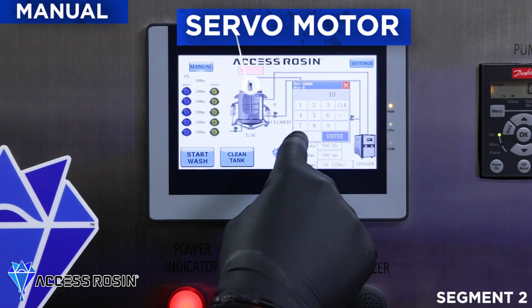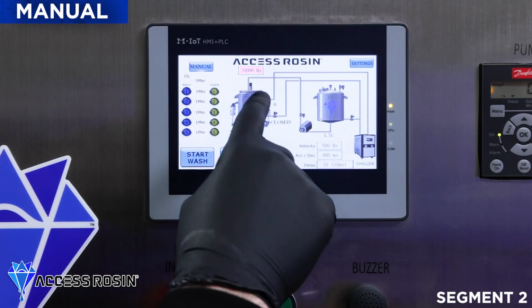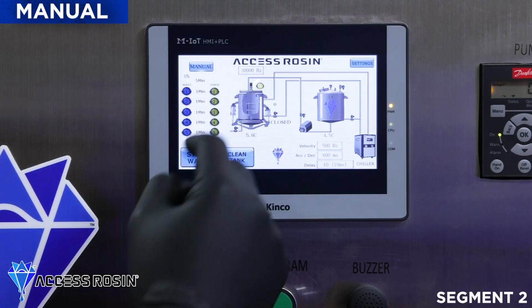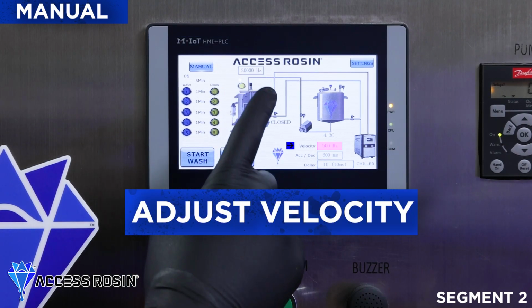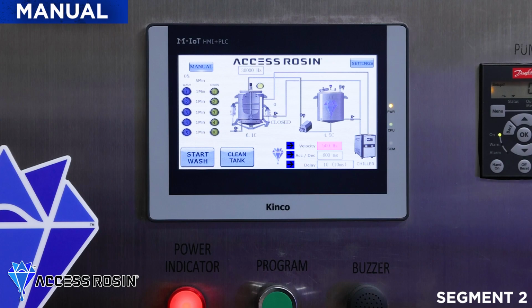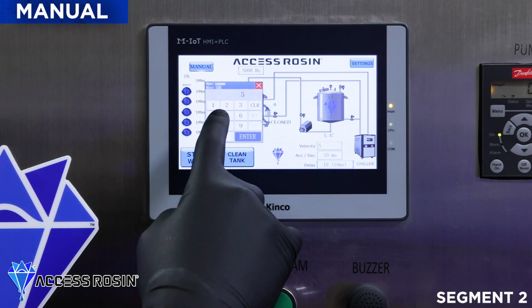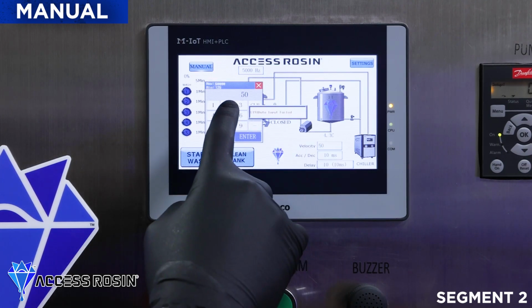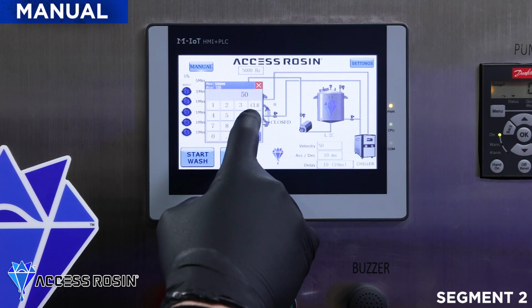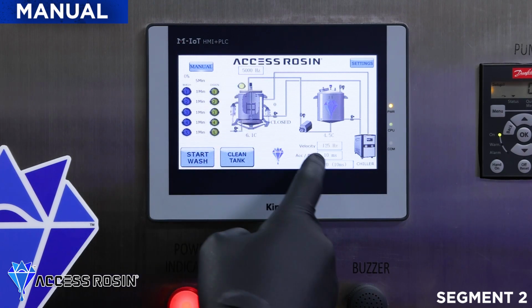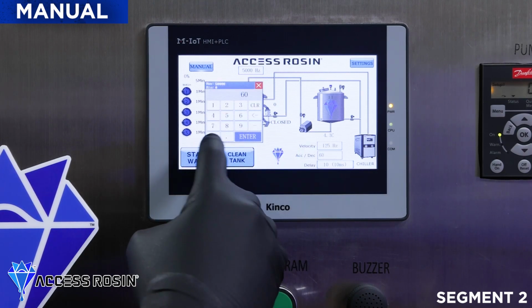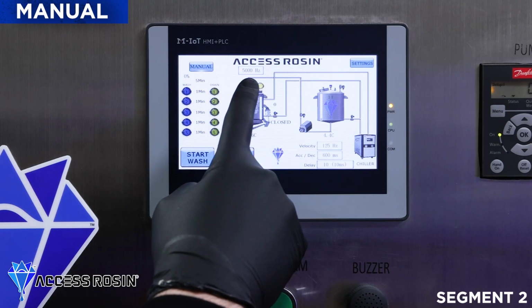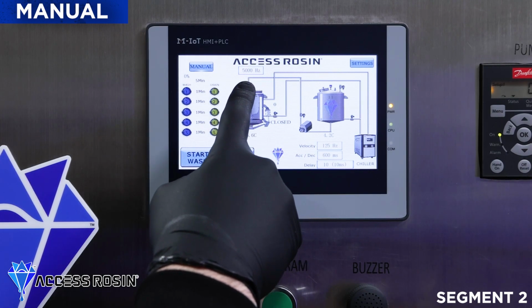The servo motor allows you to change the speed and direction of the paddle, either slowly or fast, left or right, and adjust the velocity, acceleration, deceleration, and time to get the perfect paddle agitation. By changing the acceleration to 50 and the value to 600, the movement of the servo motor can still be observed. However, it is not as aggressive as before and has a slow shimmy, allowing for fine tuning to achieve perfect paddle agitation.